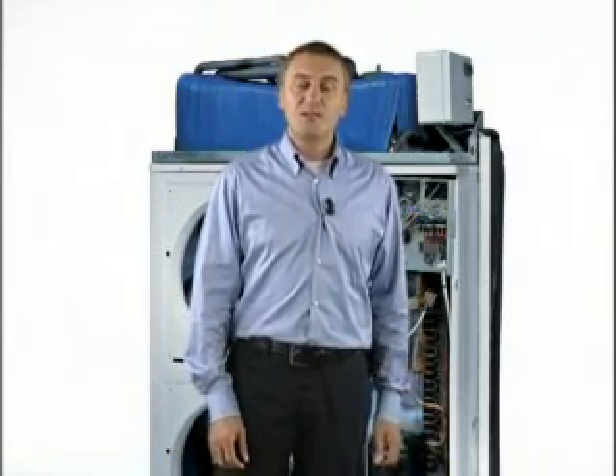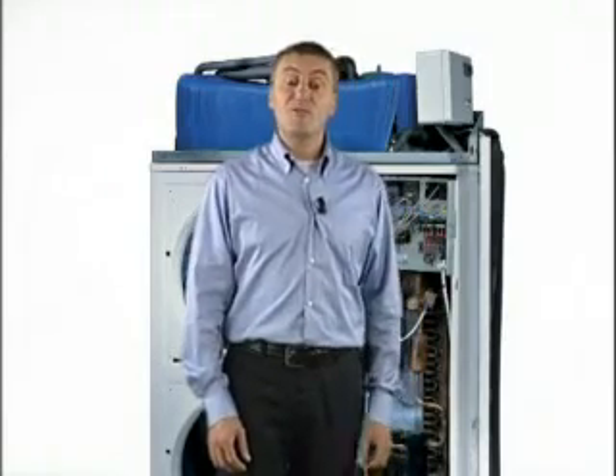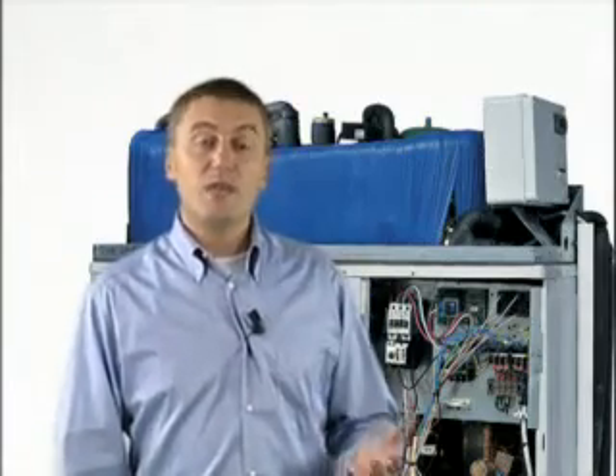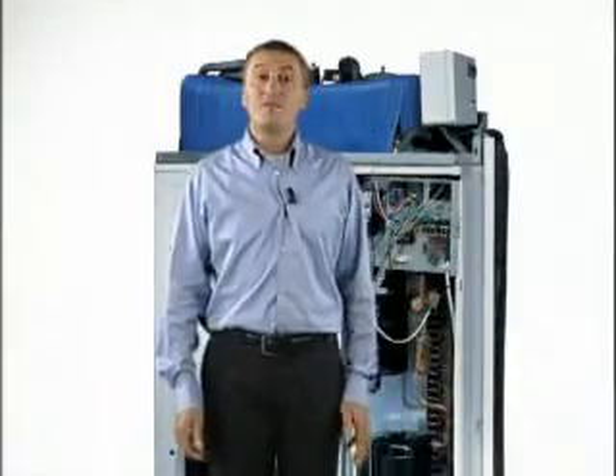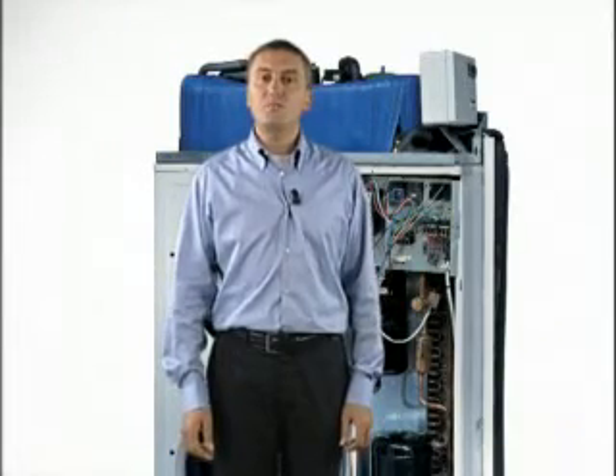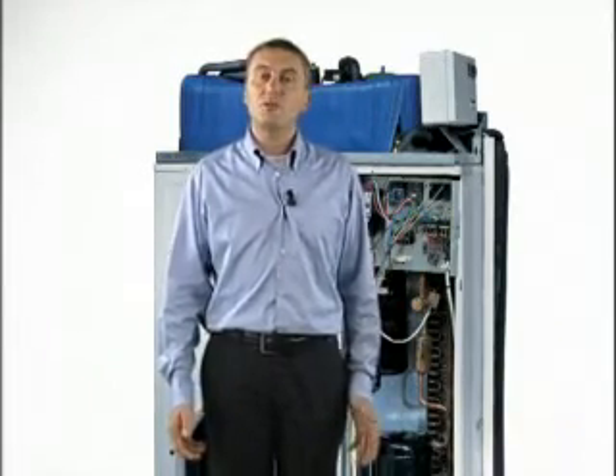Now our Climabox is installed and supplies hot or cold water to our fan coils. Climabox was created to satisfy domestic or industrial needs. It can be connected to small or medium-large systems. Climabox can be installed together with various other devices, the case, the split, the fan coil, and it has very important characteristics regarding water. Let's go and take a look at a Climabox installation with a pre-existing system with particular requirements.